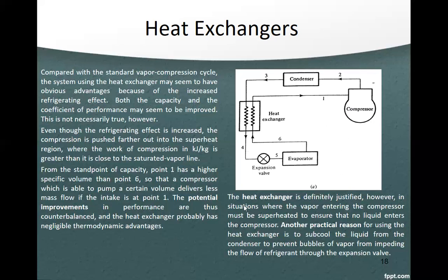ito. The heat exchanger is definitely justified, however, in situations where the vapor entering the compressor must be superheated to ensure that no liquid enters the compressor. Another practical reason for using a heat exchanger is to subcool the liquid from the condenser to prevent bubbles of vapor from impeding the flow of refrigerant to the expansion valve. So ito yung main purpose. Ito yung thermodynamic theory.